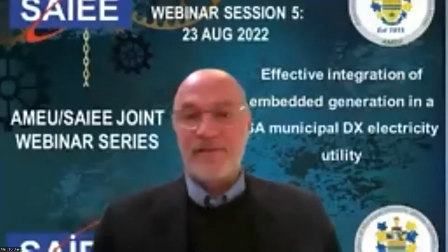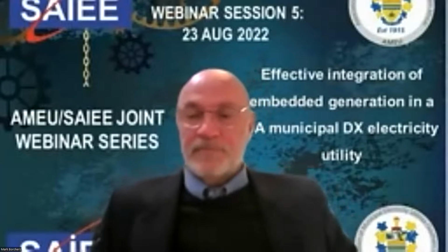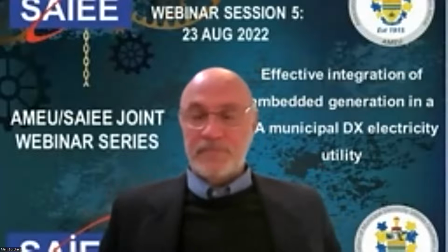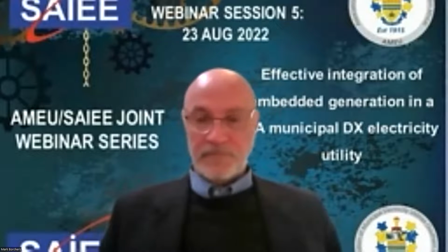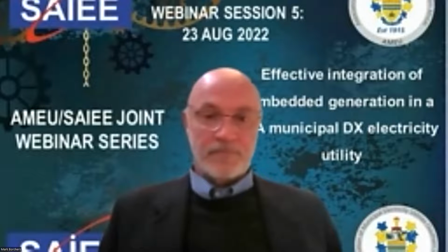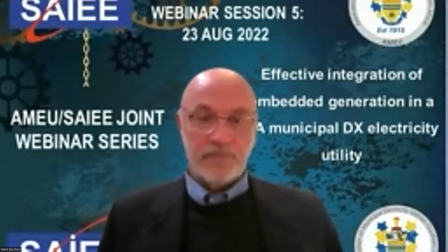Yeah, look, we've got almost, I think, above 200 megawatts of SSEG registered on our system. But prior to 2020, because I only joined this division in October 2020, there weren't really grid impact studies conducted. When I started, that's when we started doing grid impact studies for all generation above 350 kilowatts. But currently we've increased that limit to 1 megawatt. So all generators above 1 megawatt need to conduct a grid impact study.